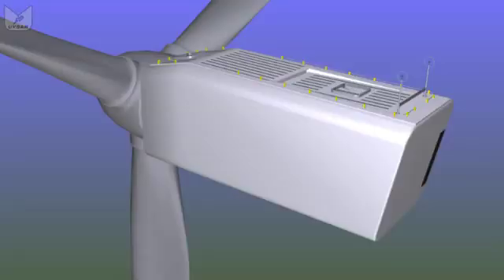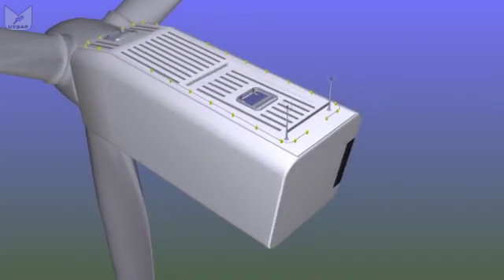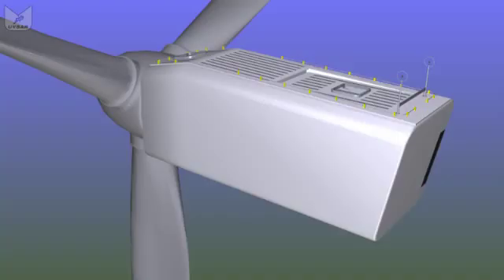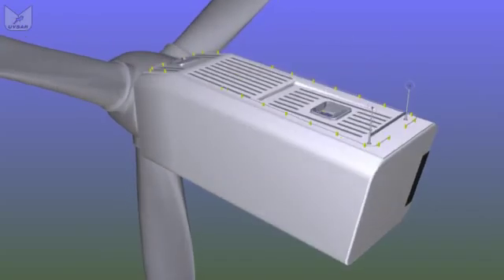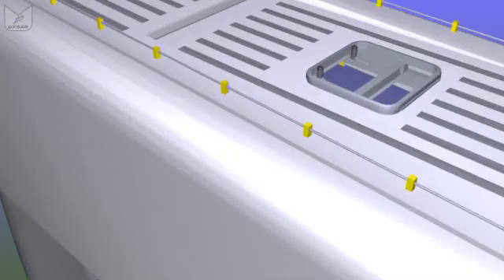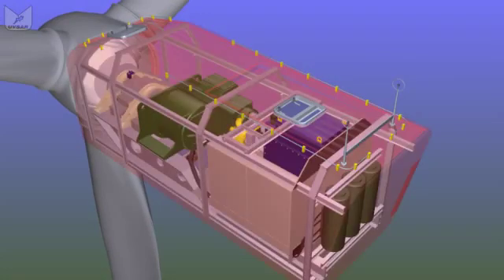And in our example, we're looking at a typical design used by a number of manufacturers, where we have a nacelle that's three meters high, two and a half meters wide, seven or eight meters long. It's a fiberglass box about the size of a bus. As before, we have our wind sensors on the roof, as far away as possible from the dirty air cast off by the blades as they spin round. This design is just a fiberglass box with a flat roof. We access the roof through a couple of skylights. Some designs are like before, big cylinder with two opening doors. Some have an entire roof section which opens, rather like an old camper van.